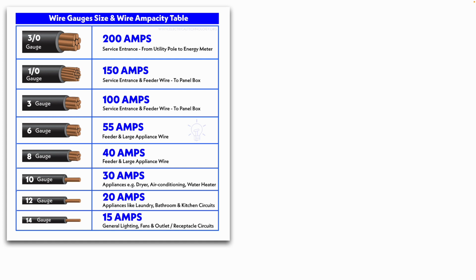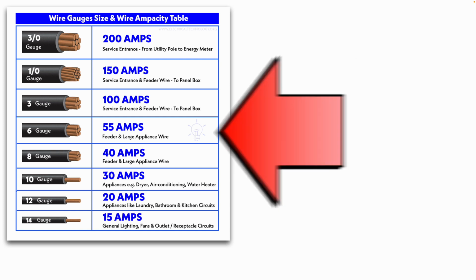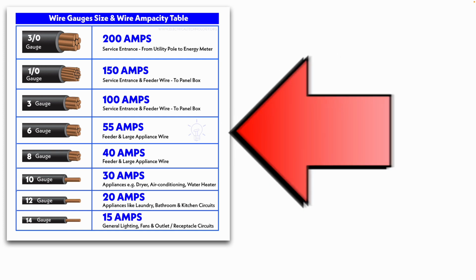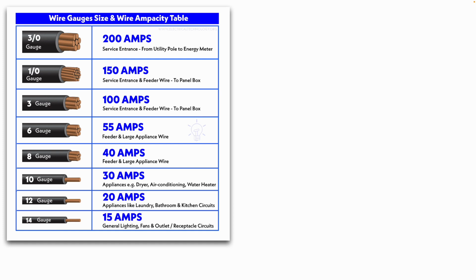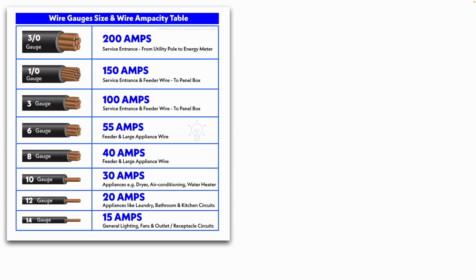So again, talking about wire ampacity, as this chart shows, that's why we're going with 6-gauge wire, because it's rated up to 55 amps. You can see if we try to downsize and go with smaller 8-gauge wire, that's only good for 40 amps, so that would not work for this example. So you want to go with a minimum of 6-gauge wire. I hope that makes sense.